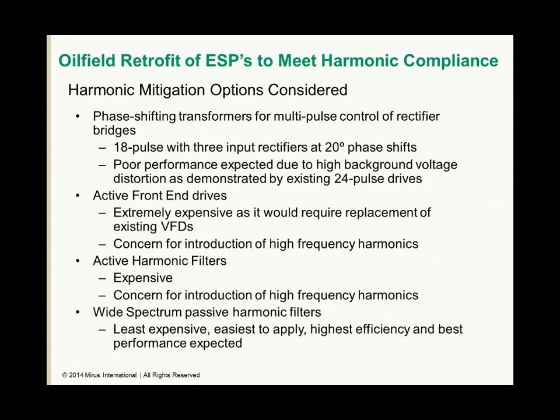Even after eliminating the resonance condition, harmonic levels exceeded the requirements of IEEE Standard 519, so harmonic mitigation was required. Various methods were considered, including phase shifting to produce a quasi-12 pulse or 18-pulse scheme, active front-end drives, parallel active harmonic filter, and the linear wide spectrum passive harmonic filter. The active solutions were ruled out due to their high cost and concerns for the high frequency IGBT harmonics that they introduced.